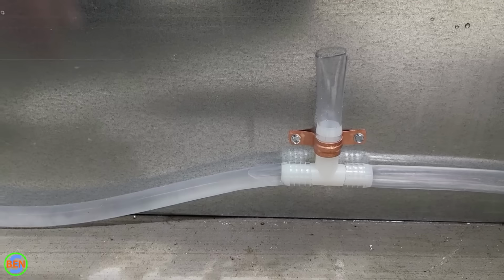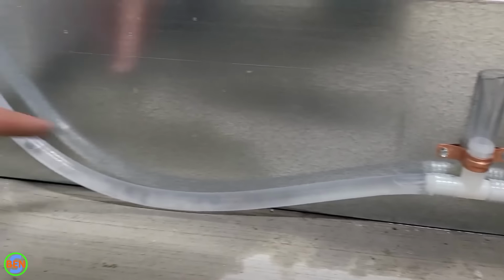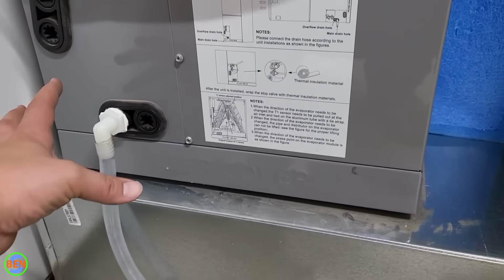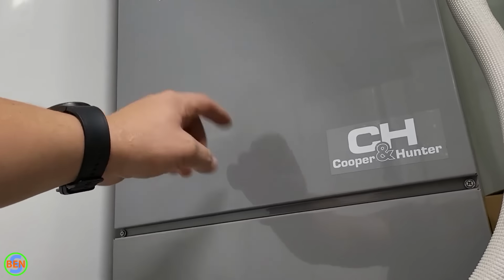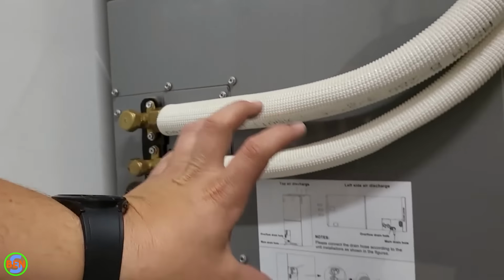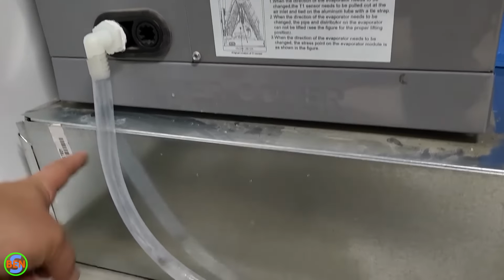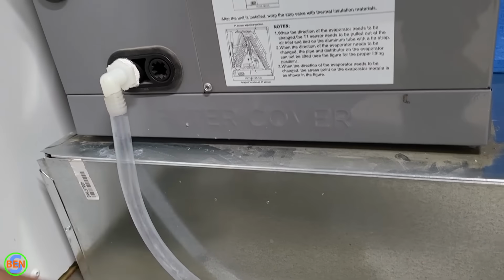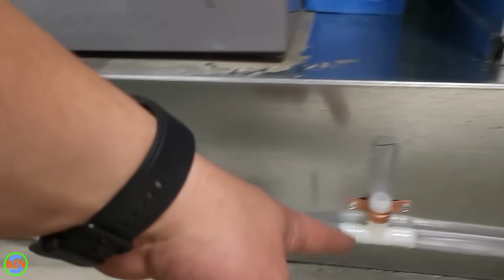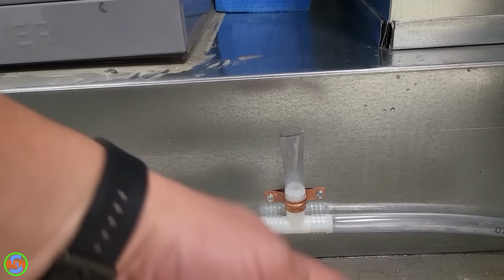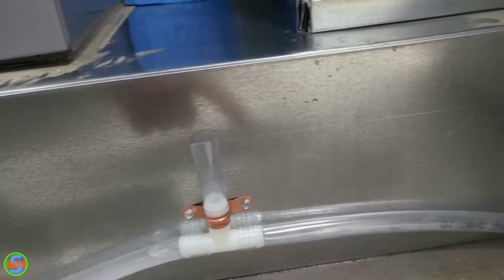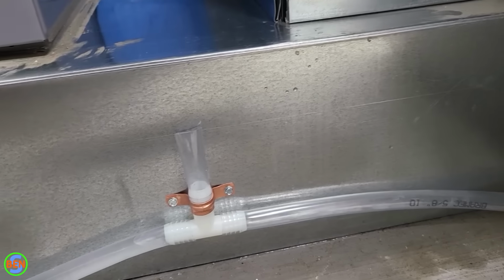And the reason for that is that we need to create a trap right on this side. This cabinet is negatively pressurized on this side because the fan is up here. So the fan is pulling the air up, which creates a negative pressure down in here. So you need to have a trap in order for this to drain properly. That is accomplished by simply holding this up a little bit, and then from here on out, we can vent it, which is going to prevent this line out here from becoming airlocked.